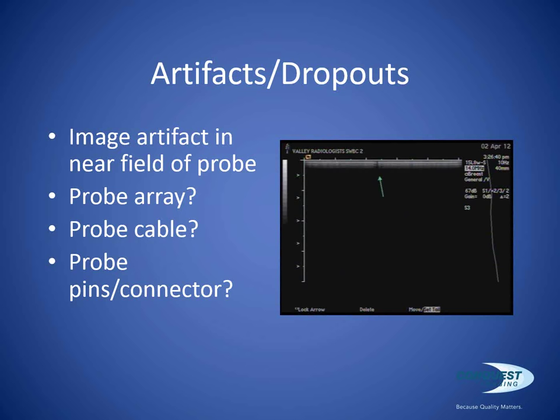We also want to look at the probes and the pins on the probe, the connector. One of the things that, as a service provider, I constantly did every time I got in front of a machine is I always examined the pins on a probe. The pins get bent easily. If the probe won't get plugged in, the typical reaction is, well, push it harder, jam it in, it'll go. And what that does is it damages pins. There's multiple problems with that. If pins are damaged, that's a bad thing. We can fix that. We have the ability at Conquest to fix bent pins on transducers.